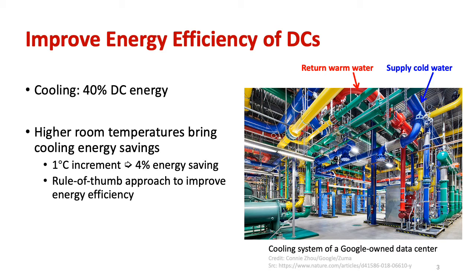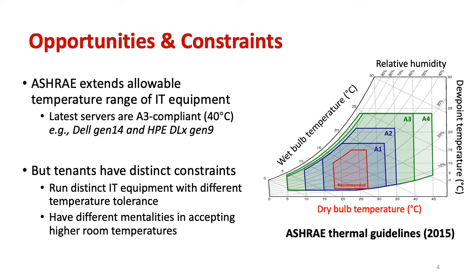From common sense, if the server rooms can operate at higher temperatures, more cooling energy savings can be achieved. From a general guideline, 1 degree temperature increment can lead to 4% cooling energy saving. So raising the server room temperature set points is a rule of thumb approach to improve the energy efficiency of data centers. To raise the operating temperatures, ASHRAE has provided the opportunities by extending the allowable temperature range of IT equipment.